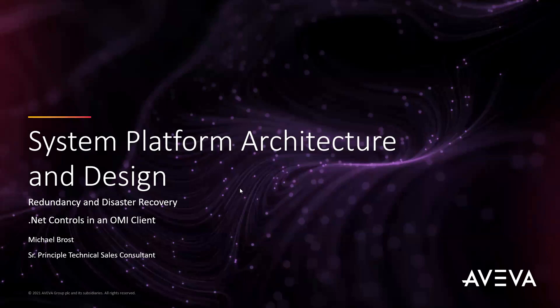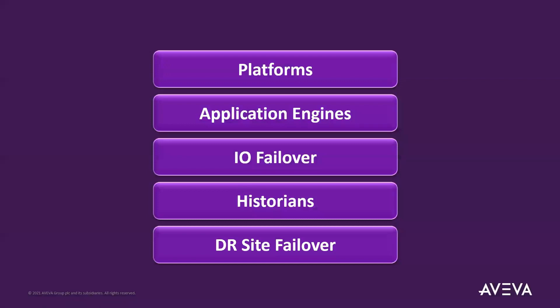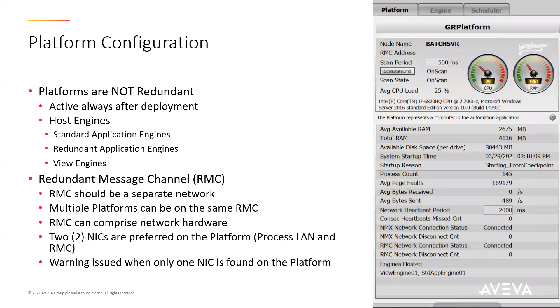We're going to start off with redundancy, and before we get into this, we'll go over a little bit of the core components of System Platform and what they do and how they contribute to the redundancy solution we typically want to engineer. The first thing is we have an object in the galaxy we call a platform. Unlike other SCADA systems where operating systems become redundant, in System Platform the platform object represents the operating system and they are not redundant — by design they're not redundant. When you deploy a platform object, it is always running, always on, always performing its role and duties.